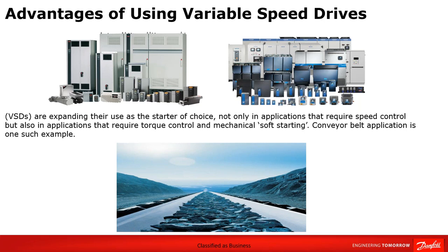It's common practice to install multiple motors on long conveyors, and the drives need to ensure load sharing between each motor for a reliable operation and to maximize the belt life. The VLT and the Vacon drives include both what we call master-master, and what we're going to look at today, the master-follower control solutions for this. Selection of the control solution depends on the configuration of the conveyor drives on the conveyor. So for example, all the drives at the head end, or drives at both the head and the tail end.